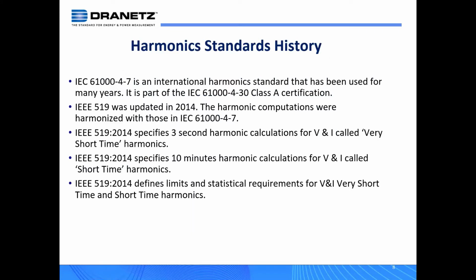So just as a review of the harmonic standards, there's a standard that's been around and in use for many years, certainly in Dranetz products since the mid-2000s or so, and that's called IEC 61000-4-7. And that is an international harmonic standard, and it's part of the IEC 61000-4-30 requirements. And if you're Class A compliant with 61000-4-30, you inherently comply with this 61000-4-7 standard. It is a substandard that specifically is focused on harmonics.